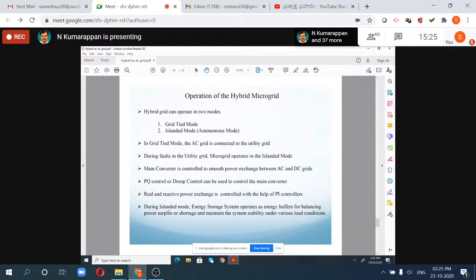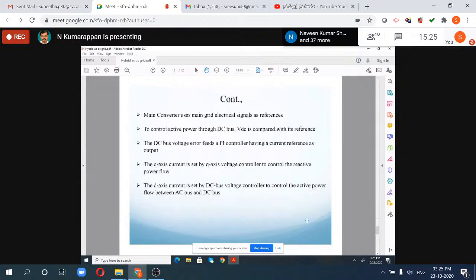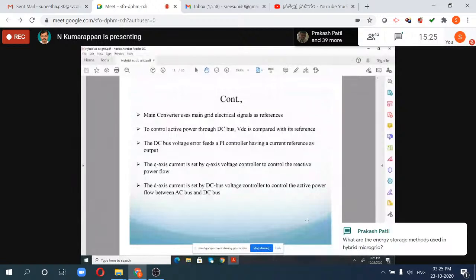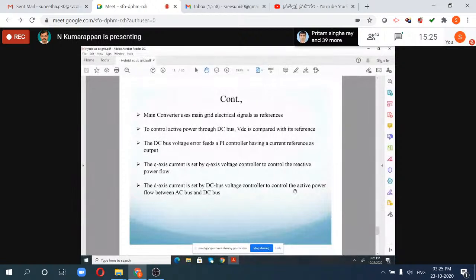During islanded mode, the energy storage system operates as an energy buffer for balancing power surplus or shortage and maintaining system stability under various load conditions. Now, continuing, the main converter uses the main grid electrical signals as references. We always require references; only then do the converters work effectively. To control the active power through the DC bus, VDC is compared with its reference.